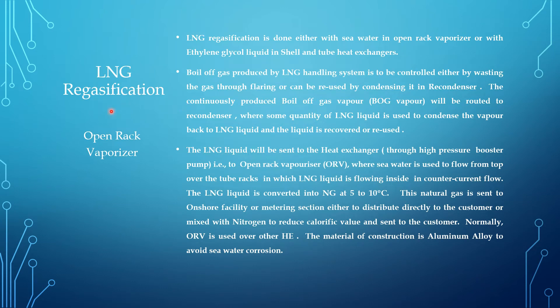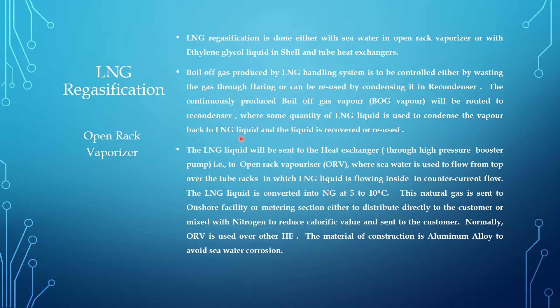LNG regasification is done either with seawater in an open rack vaporizer (ORV), or with ethylene glycol liquid in a shell and tube heat exchanger. Boil-off gas (BOG) is produced in the LNG handling system, whether in a pipeline or storage vessel. This BOG is controlled either by flaring or by reusing it — routing it to a recondenser where LNG liquid condenses the vapor back to LNG liquid.